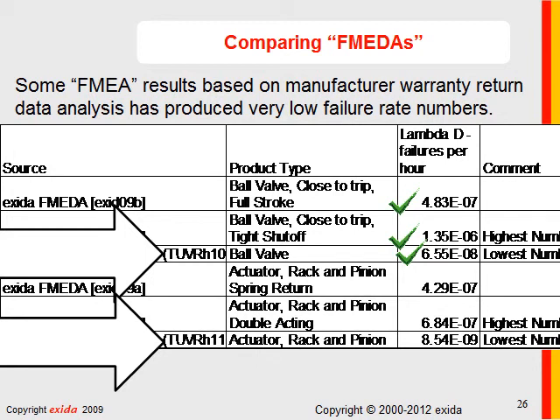For actuators, exida has a spring return rack and pinion actuator at 4.29e-7 and a double-acting rack and pinion actuator at 6.84e-7 failures per hour. Another set of data based on an FMEA using manufacturer's warranty data showed 8.54e-9 — approaching two orders of magnitude too low. If someone uses a particularly optimistic failure rate, they could be designing a system that is not safe enough.